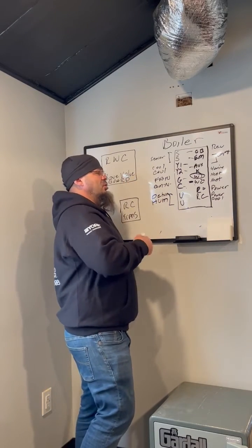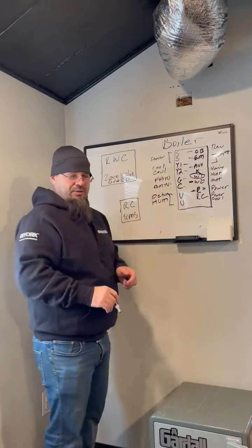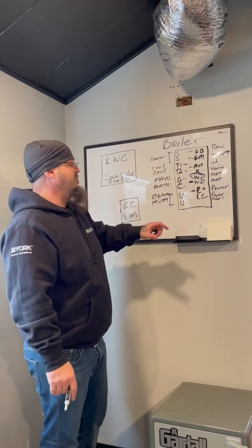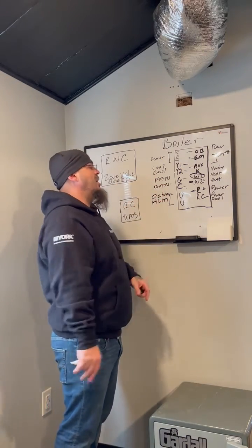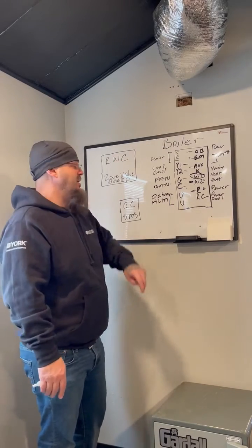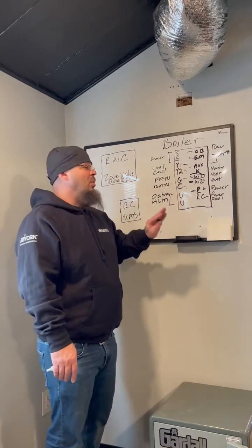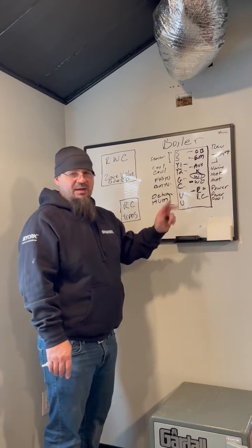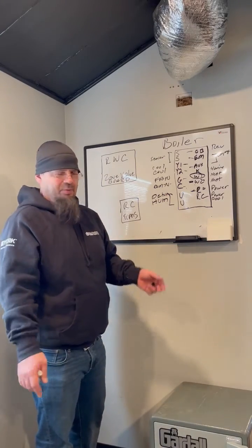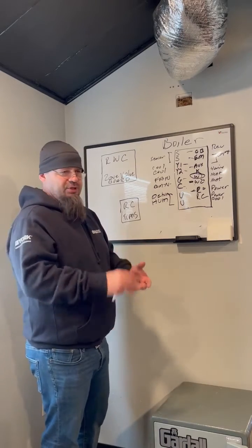As far as just installing a thermostat, this is as simple as it gets. Take a picture. You're only going to have 2 terminals in this whole thing that are going to run the thermostat. You're going to make sure to turn the boiler off, pull the base plate off, hook the 2 wires up, set it level, and then put the face on and program it for hydronic heating. It is super, super simple as far as wiring goes. When we get into setting the base plate and all that, it's all the same. It has its pitfalls, but it's relatively simple. A couple of anchors, you screw the base on level, and then push the thermostat on there.